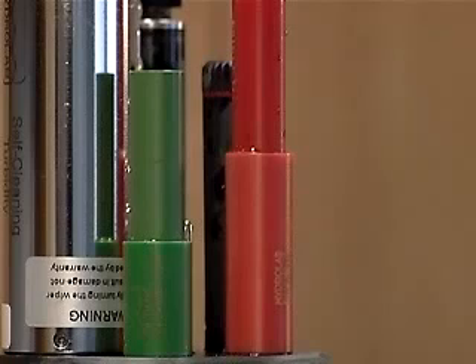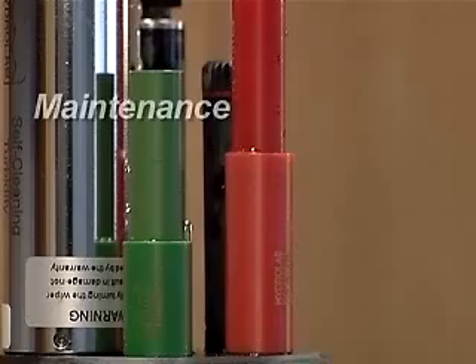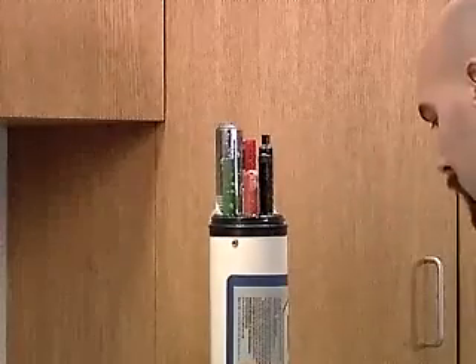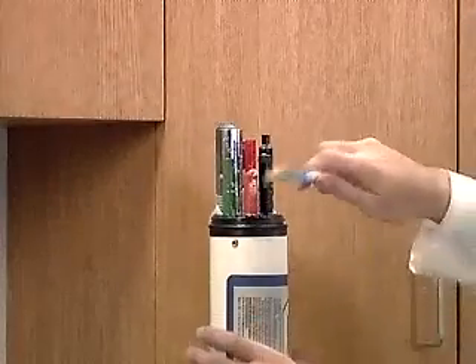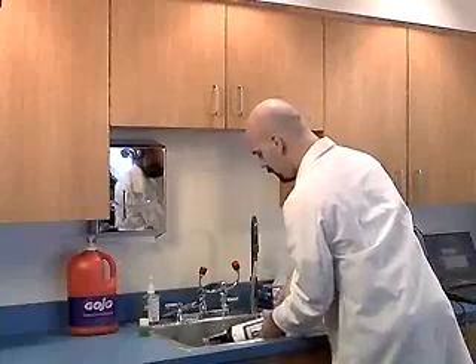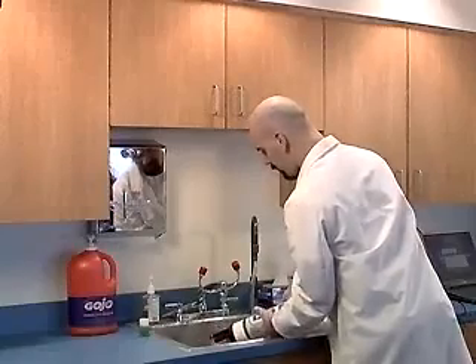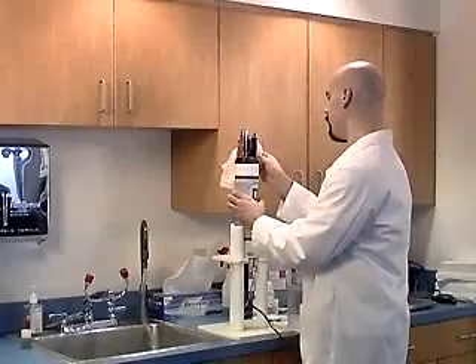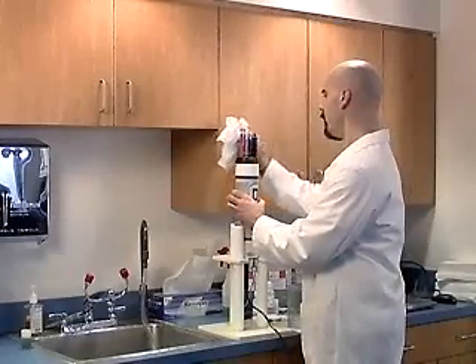The chloride sensor can be used in fresh or brackish water. However, the chloride ion levels in seawater will exceed the detection range of the sensor. Maintenance. The only maintenance required for the ion sensors is to keep them clean. Over time, the silver chloride pellet will deplete itself, and the tip must be replaced.